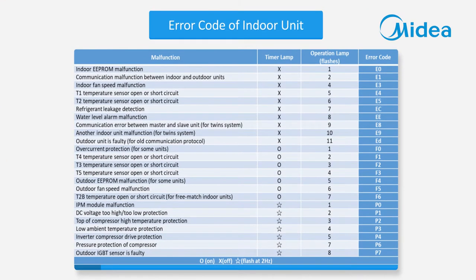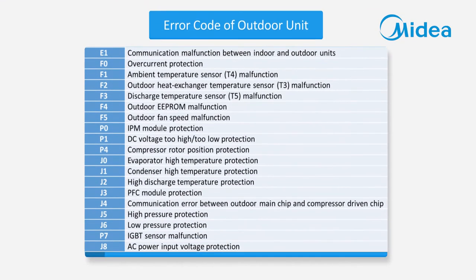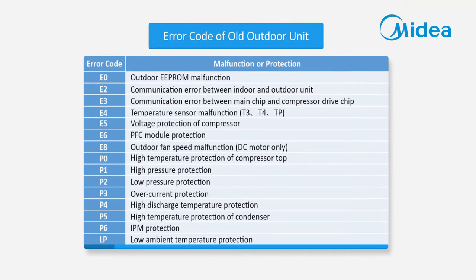When an error occurs, the error code will be shown on both the display board of indoor units and the digital display of outdoor units. This table lists all the error codes of indoor units you may encounter. For indoor units without digital display, pay attention to the status of running light and timer light. This table lists all the error codes of outdoor units you may meet. If the indoor unit shows ED, the outdoor unit must be using an old communication protocol, and the error codes of old outdoor units are shown in this table.